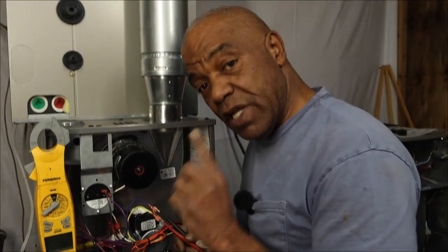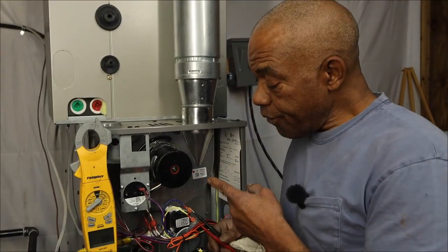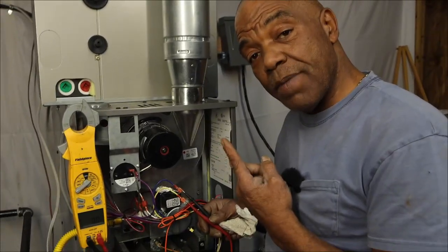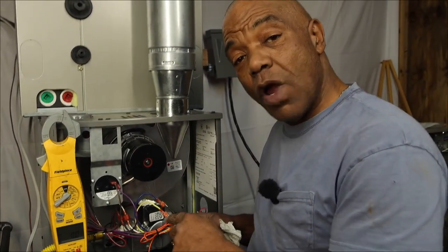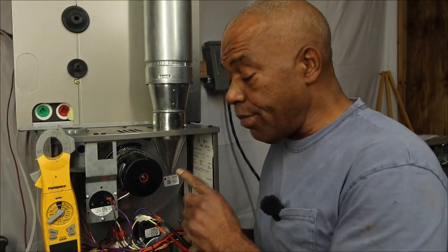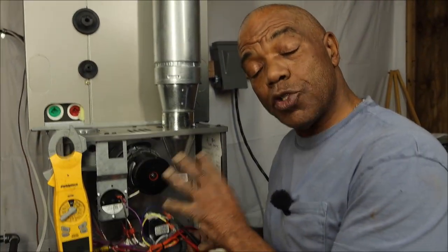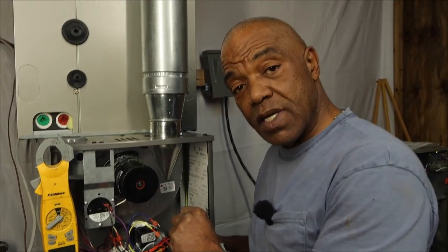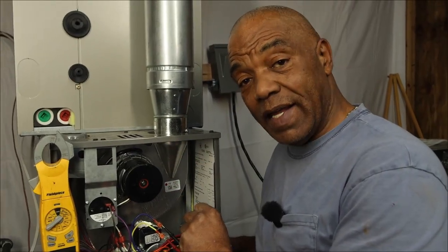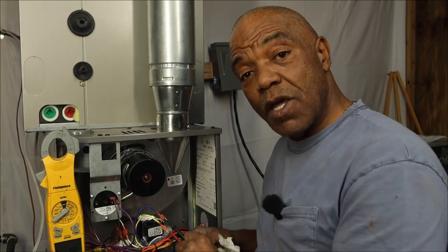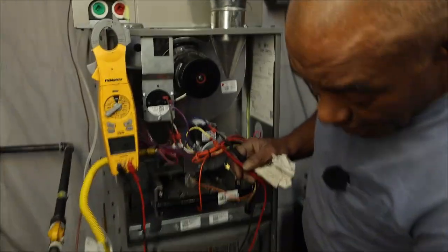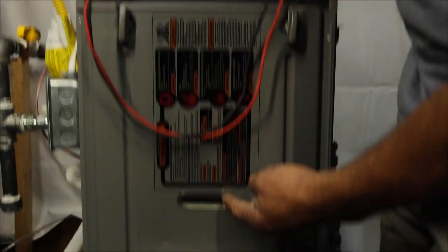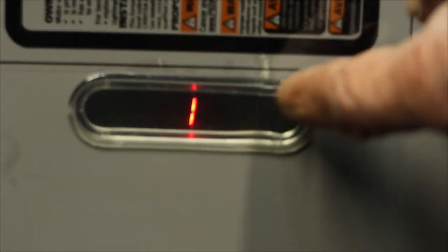It's tried 3 times. Okay, it's trying a 4th time. Apparently, I interrupted the power in between one of them. Typically, it will try to fire 3 times. And if it does not ignite on the 3rd effort, it'll lock itself out, and the LED light that we were talking about earlier will begin to flash an error code.